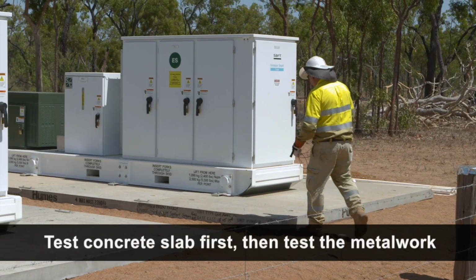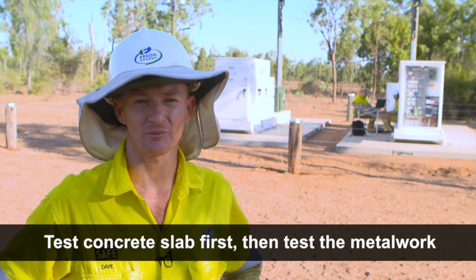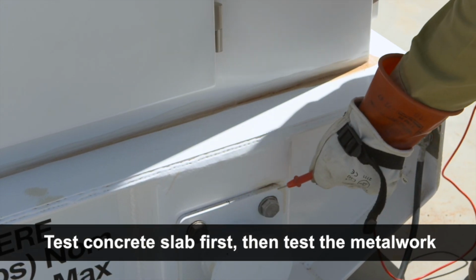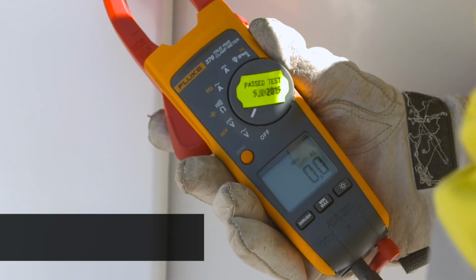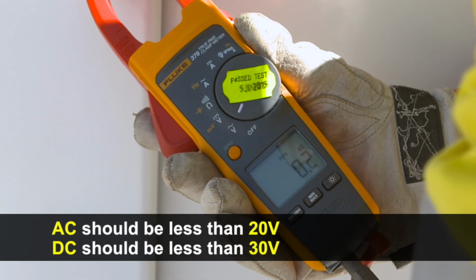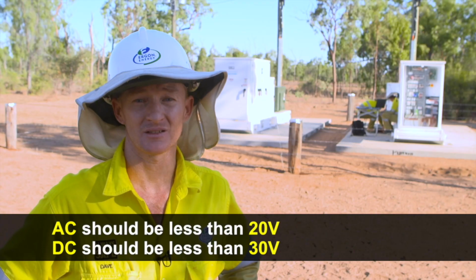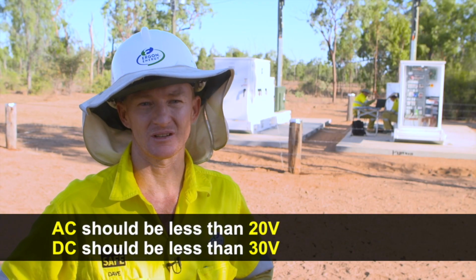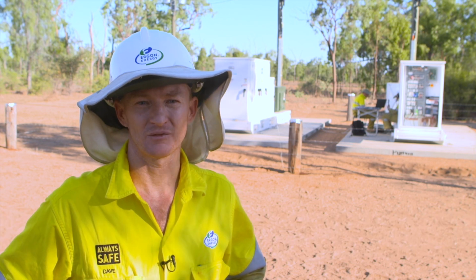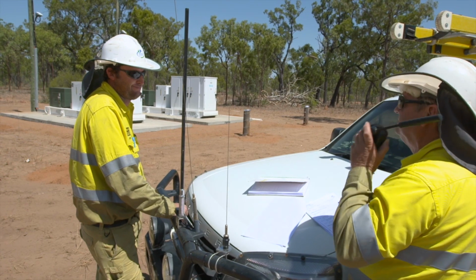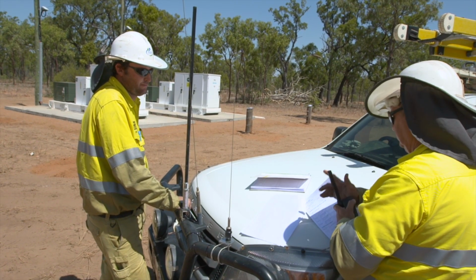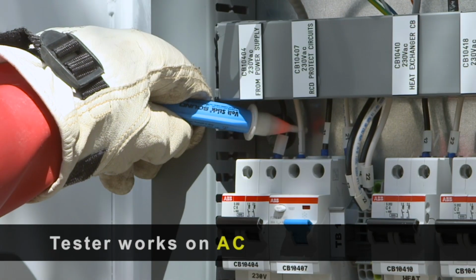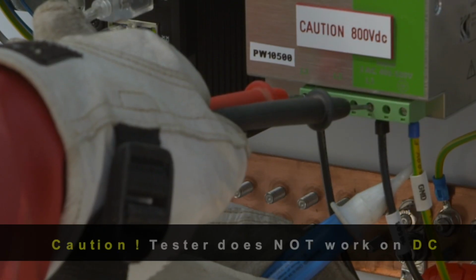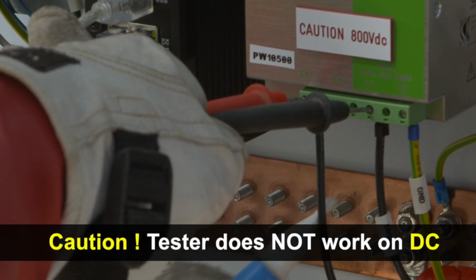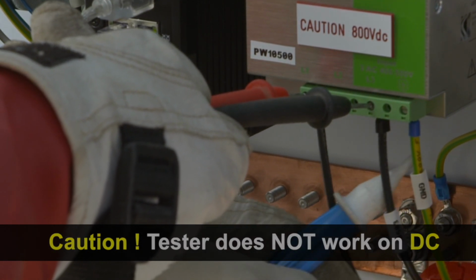Install a temporary earth stake at least 2 metres from the concrete apron around the GUSS unit and test from the earth stake to the concrete apron and then the GUSS metalwork. The AC should be less than 20 volts and the DC should be less than 30 volts. It is safe to approach the unit if those voltages are less than those values. If the voltages are higher, stay clear of the unit and advise your local region SME or GUSS engineer. Remember, test pencils and proximity devices will not indicate the presence of DC voltages, so shall not be used.